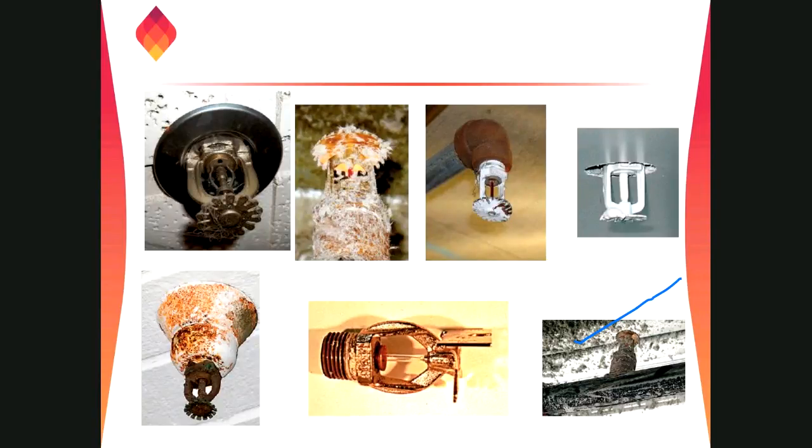And how about this one on the left? Yeah, nothing wrong with this one. Shiny and clean, mashallah. Yeah, everything is wrong with this one. What happened? They put the sprinkler into the piping before the finishing of the building, right? A sprinkler system should be installed last, when the building is completed, painting, everything done. They put it in at the beginning, and then they are doing concreting, finishing, and the masonry works for the construction, and everything is destroyed, right?